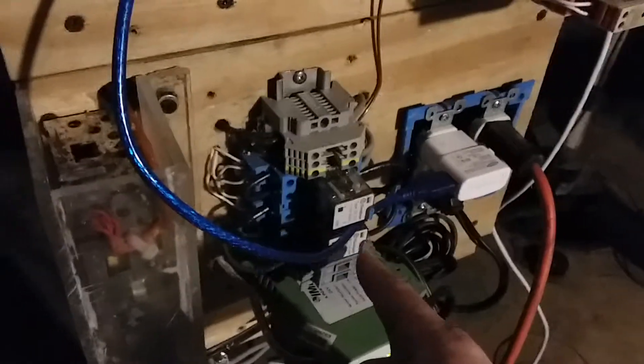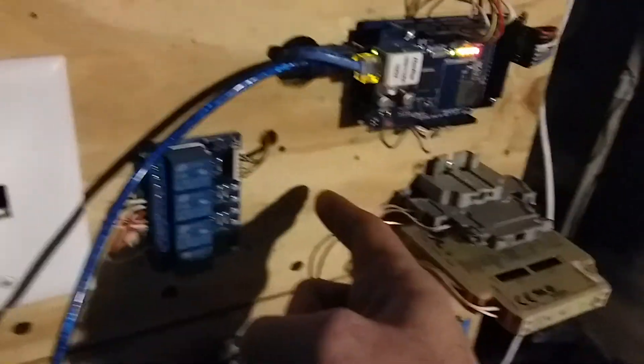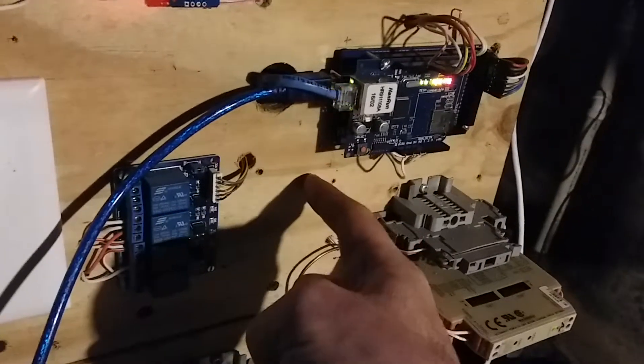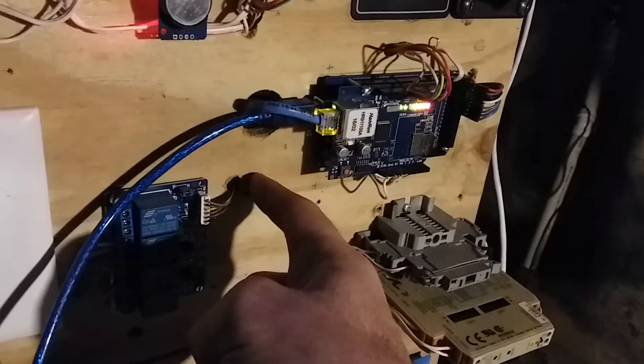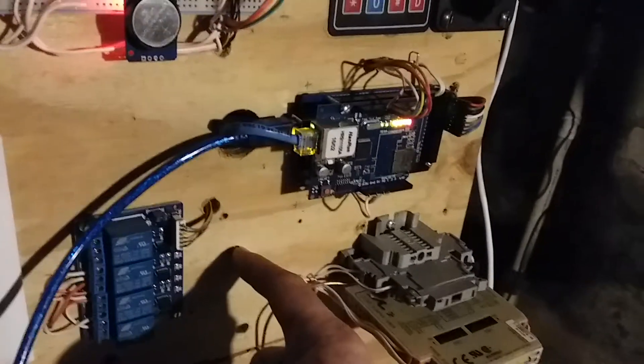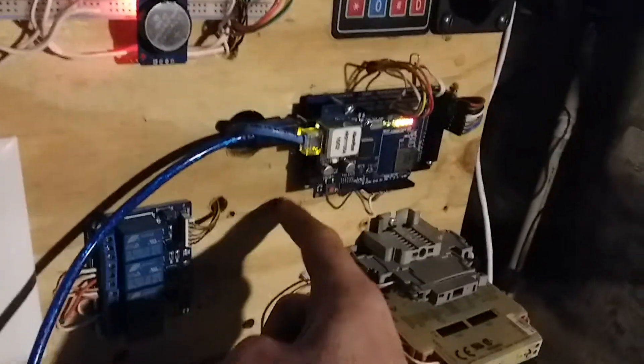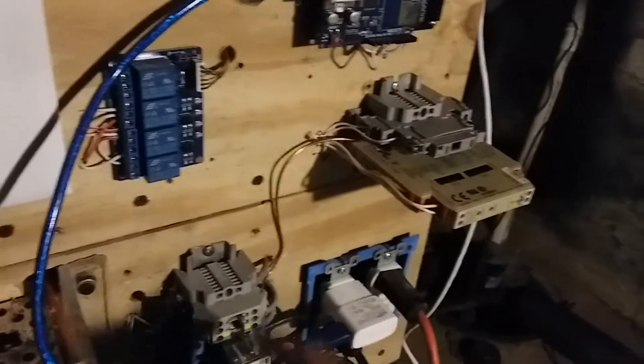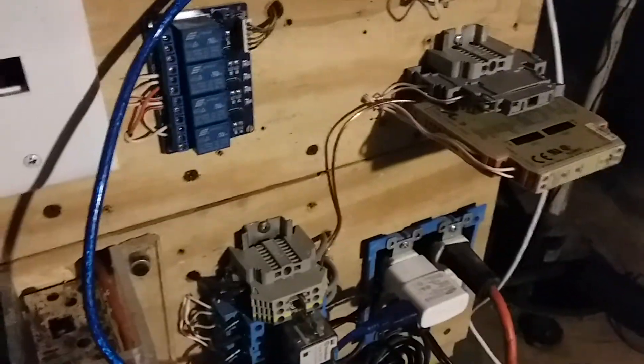These small relays toggle larger relays — I'm not driving the pumps directly off the little relays. I'm using larger relays and double-contacting them. For anyone familiar with industrial relays, the signal comes in on terminal 14, out on 11 (the common), then to the second common on 21, and out on 24. I'm using both sets of contacts on a dual-contact relay to handle more current.